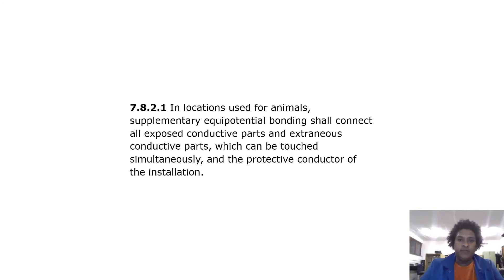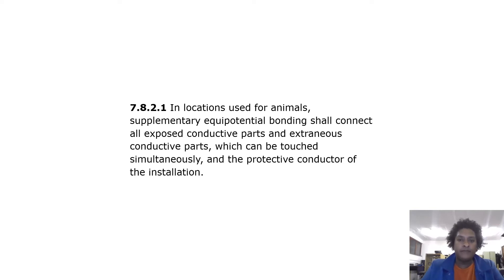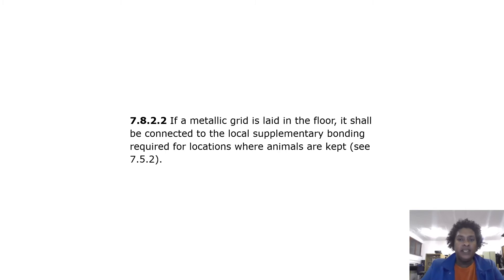Supplementary Equipotential Bonding: in locations used for animals, supplementary equipotential bonding shall connect all exposed conductive parts and extraneous conductive parts which can be touched simultaneously, and the protective conductor of the installation. If a metallic grid is laid on the floor, it shall be connected to the local supplementary bonding required for locations where animals are kept.